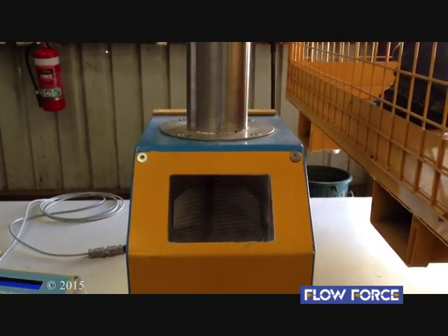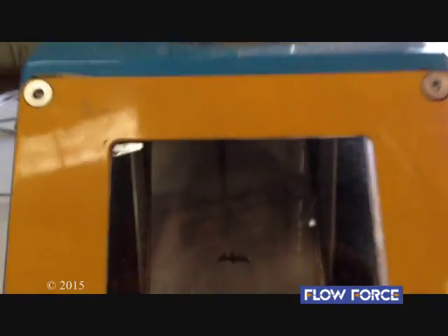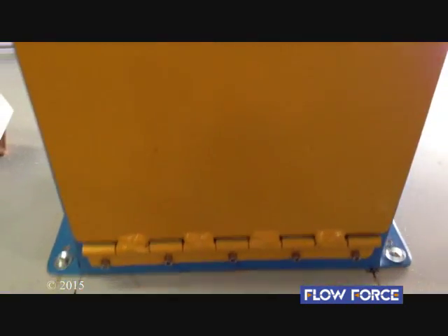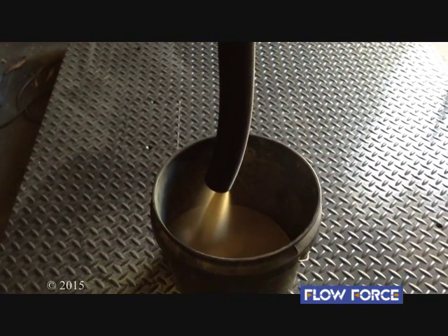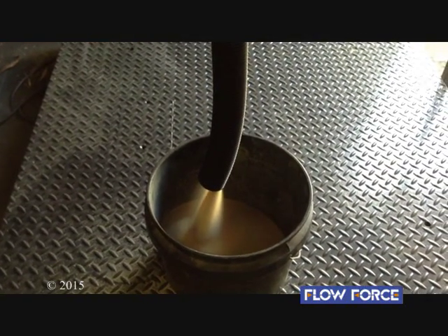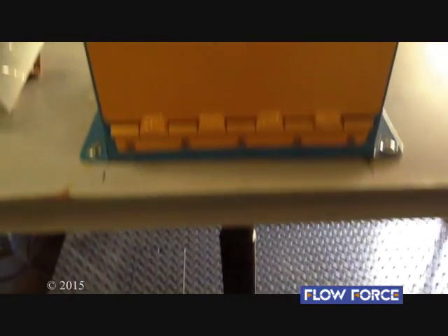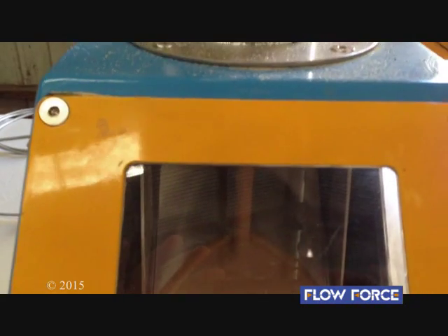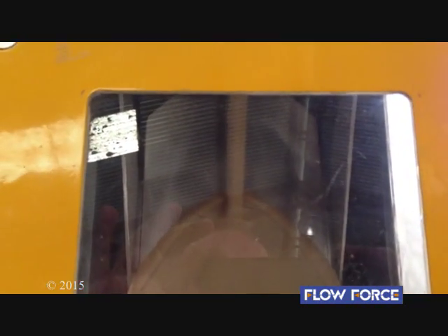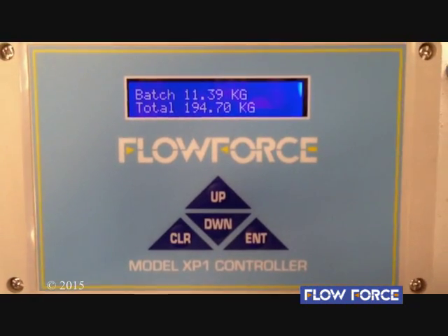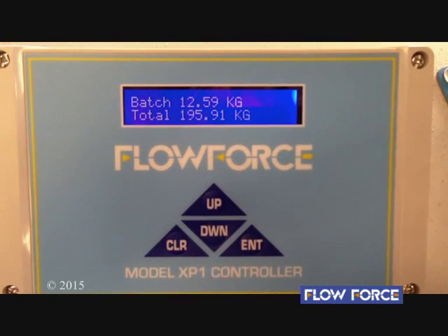We're now ready to start our first test, so we'll begin to feed some product through our impact weigher. We have a little demonstration jig set up here where we pour sand through an orifice into our impact weigher, and we'll begin doing that now. We'll see the flow come through, and it'll flow through our weigher into our test container, and we'll put a batch through and compare the outputs. You'll see while this is flowing through on our XP1 controller, the batch is going up, the total's going up.